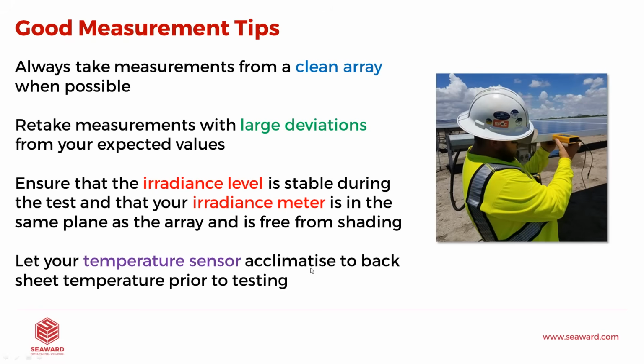Some good tips for taking good measurements: we need to take these measurements from a clean array whenever we can. This will give us the most accurate results. And we should also retake measurements with large deviations from our expected values. So I mentioned earlier, you've got in the back of your mind, okay, well, I've got 10 panels. It should be 800 volts. I'm actually getting 600 here. That seems to me like there's a problem.